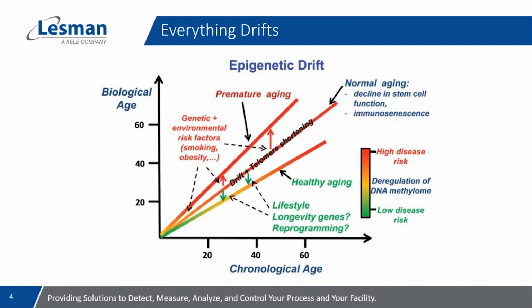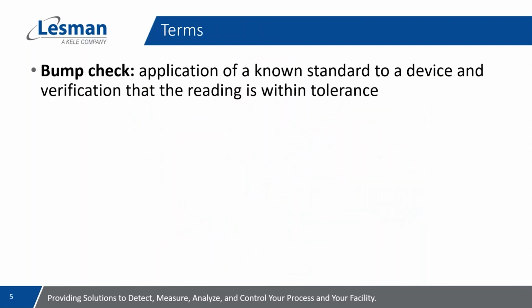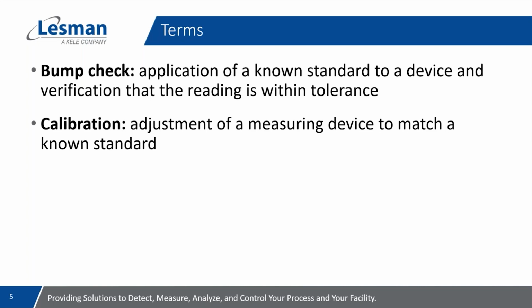Let's look at some common maintenance activities used on these gas detection systems. First is a bump check, a confirmation that the sensor response to the target gas is as expected. I put 20 ppm on the detector and confirm that it reads 20 ppm plus some tolerance. Next is an actual calibration, an adjustment of the output to match your calibration standard. Most of us are familiar with these activities from experience with portable gas systems. You bump before use, you calibrate at some interval or as needed. But if we applied the same logic to permanently installed systems, we'd be bumping them every day. Not at all reasonable. This is the spot where the new sensor technologies fill the gap.